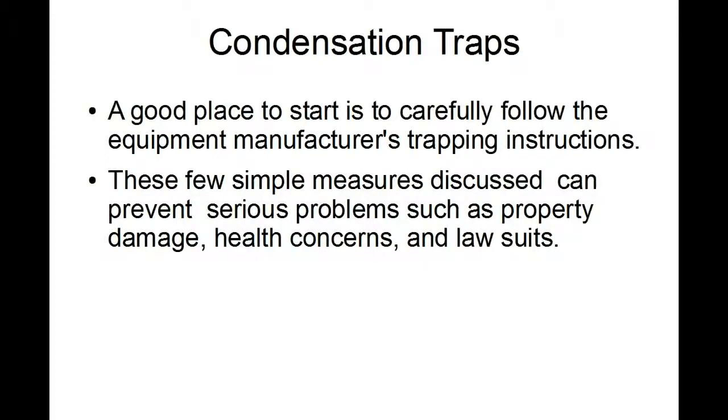A good place to start when you're looking at condensation drain issues is the manufacturer's installation guides and trapping instructions. They'll have detailed instructions in there of what trap to use, how to trap and what to do. They're different for each manufacturer, so make sure that you can locate those. If you can't find the installation guide, then you need to get online or get on tech support and find out if you suspect that the trap is incorrectly designed. By paying attention to that and the things we talked about, you can prevent some really serious problems like the ceilings caving in.